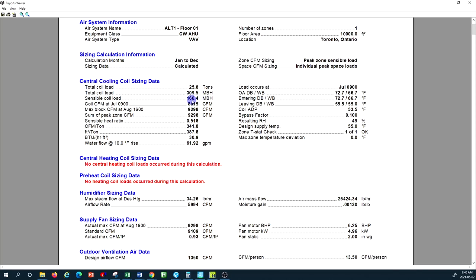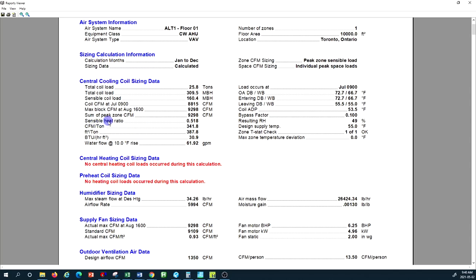Subtracting sensible load from total load gives latent load. For water flow, the system requires 61.92 GPM with a 10-degree temperature rise. If the chilled water supply is 45°F, the return chilled water temperature should be 55°F to achieve that cooling demand for that zone.